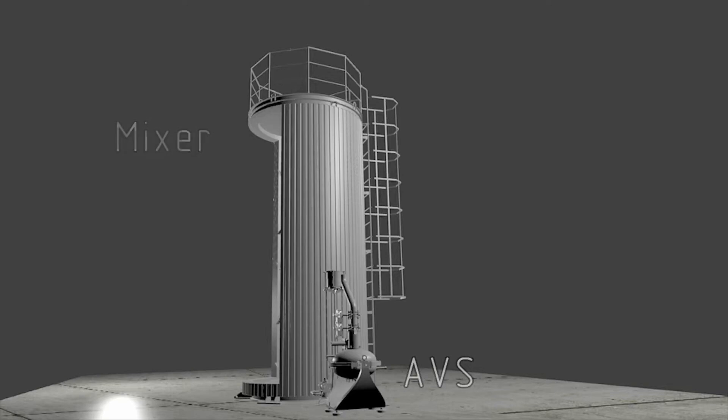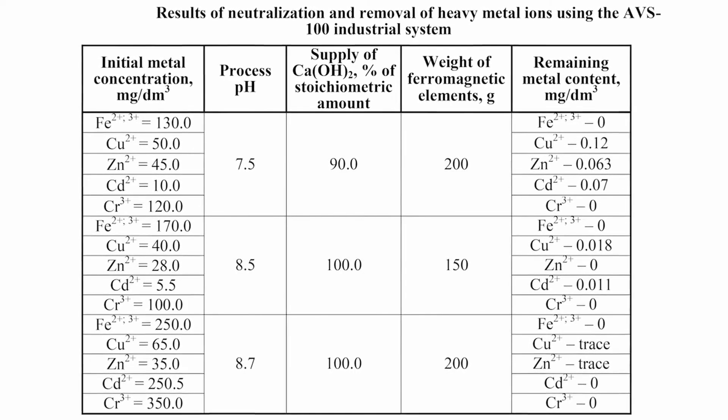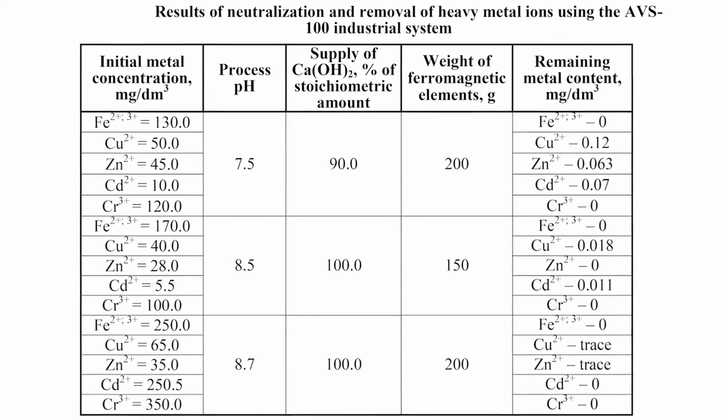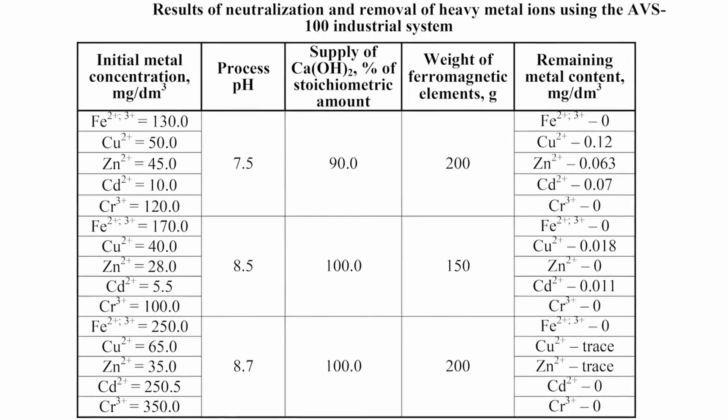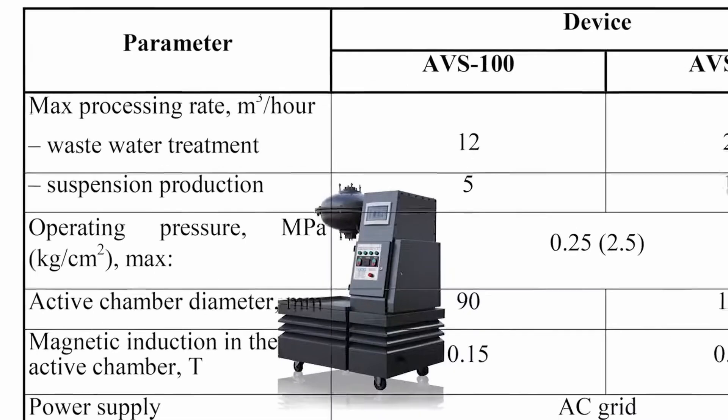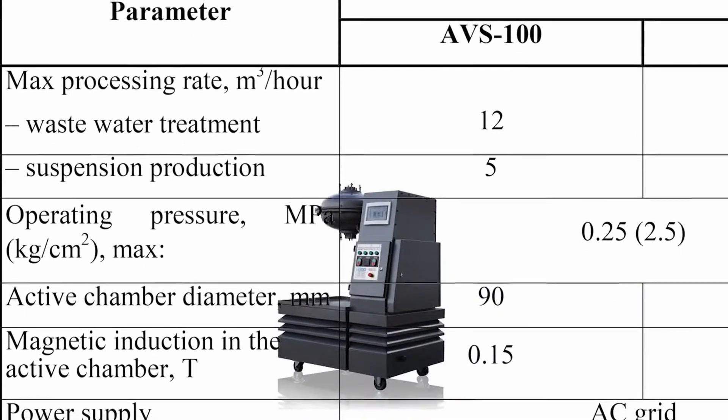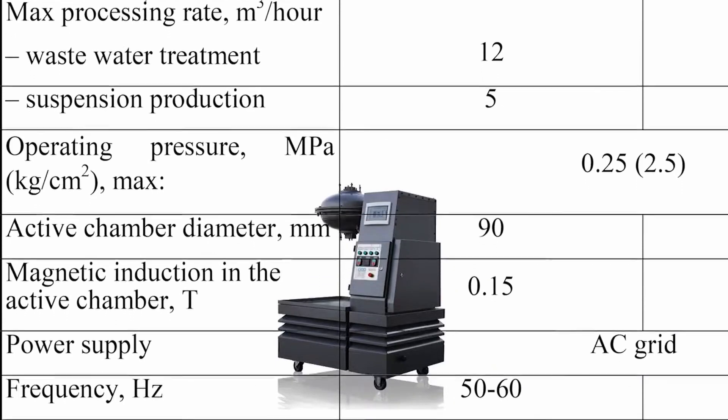Specifications of electromagnetic vortex layer devices. Characteristics of AVS-100 device: the maximum capacity during wastewater treatment is 12 cubic meters per hour; when obtaining the suspension, it equals 5 cubic meters per hour; maximum operating pressure in the chamber, 0.25 megapascal; rotation speed of magnetic field, 3000 revolutions per minute; power consumption, 4.5 kilowatts per hour.